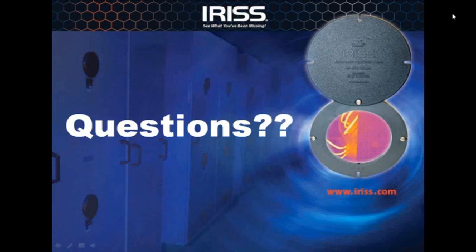Right, we supply all of those companies directly as a manufacturer, but what it boils down to is the requirements of, first and foremost, most people come up with UL. What's the UL requirement? And then are the products. So first and foremost, the products you fit must meet the requirements of UL, IEEE, and any of the switchgear companies directly. So UL clearly state that, even though our products may be UL listed, if you cut a hole, if you change the original design certification of the switch, then really you need to get it reclassified.